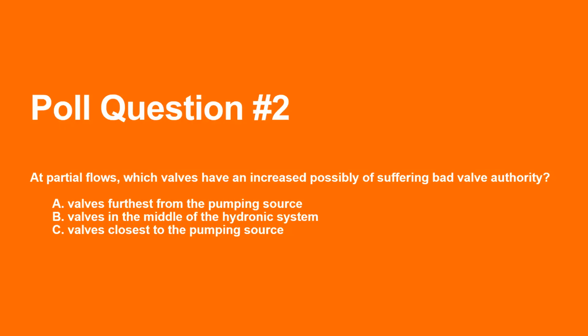So let's move to poll question 2. If you guys can pull that up. At partial flows, which valves have an increased possibility of suffering bad valve authority? Valves furthest from the pumping source, valves in the middle of the hydronic system, or valves closest to the pumping source. I'll give you a few moments to answer. So the correct answer was C, valves closest to the pumping source, correct.